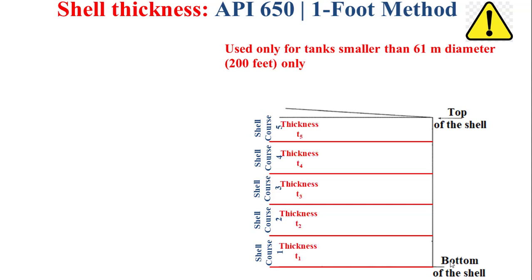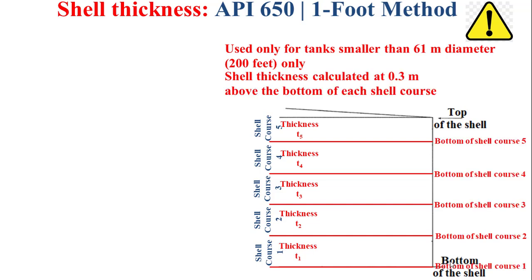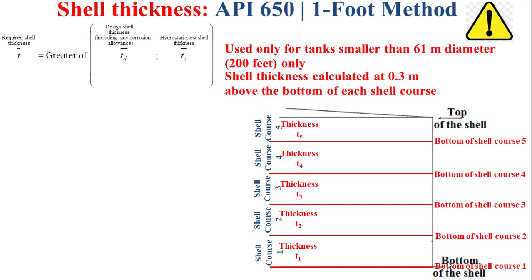The shell thickness calculated by the one-foot method is determined at 0.3 meters above the bottom of each shell course.